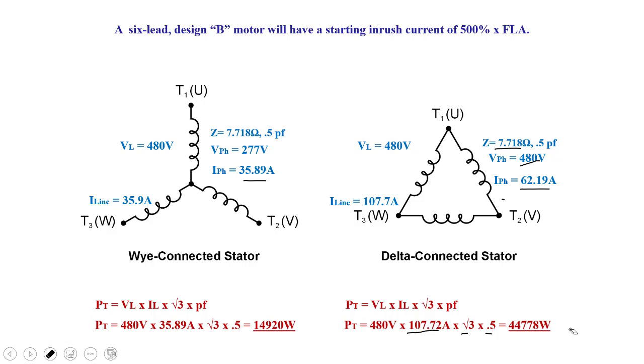Now if I convert that to horsepower, I take 14,920 divided by 746, and we're about a 20 horsepower motor in Y. Do the same thing for delta, and we're looking at roughly a 60 horsepower motor when it's connected in delta. So same motor, reconnected from Y to delta.